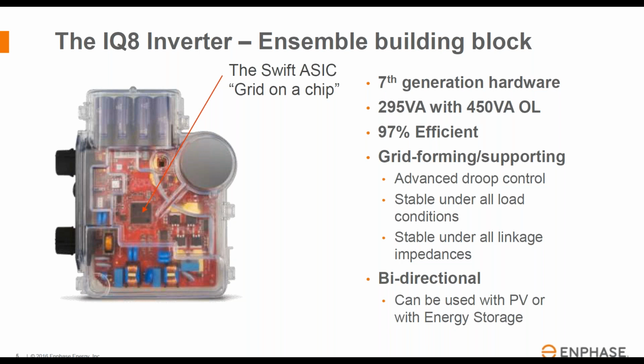It's roughly 97% efficient in either direction, either taking DC energy and creating AC, or the other way around, if it's charging a battery, for example. And it's what we call grid forming or grid supporting. It can operate in grid-tied mode, where it's supporting a grid, or in a grid-forming mode, where it's essentially creating the grid on its own. It does that by using advanced grid controls. So far, it's stable under all load conditions and with all linkage impedances. That's really important, because if you have a local system with undefined impedances between individual systems, you need to make sure the system is fairly robust and can accommodate wide ranges of the impedances you might find between them. Next slide, please.